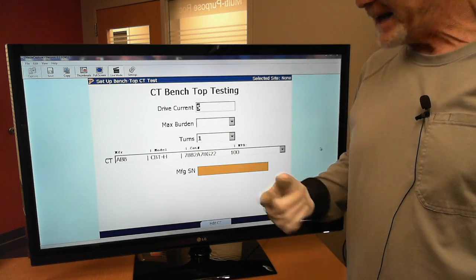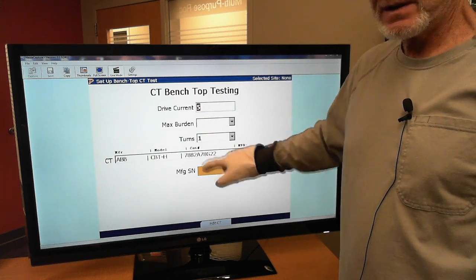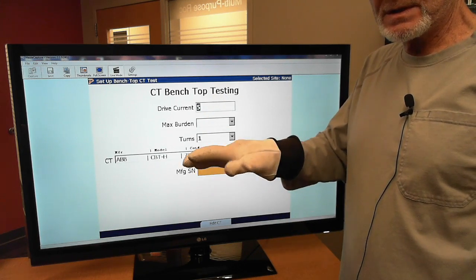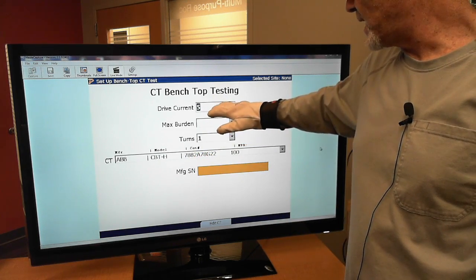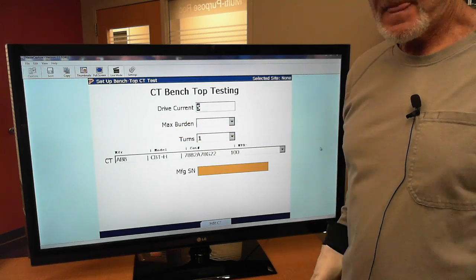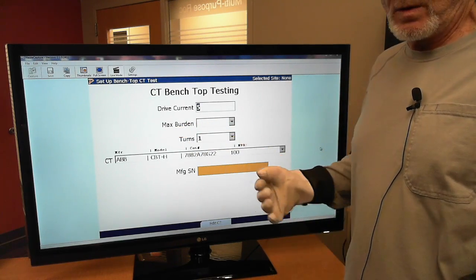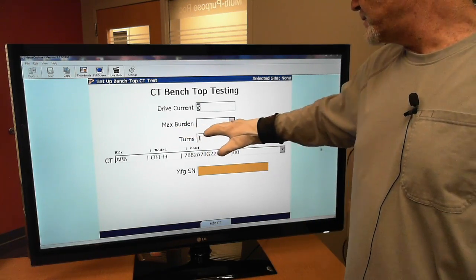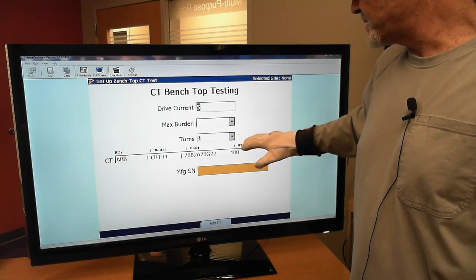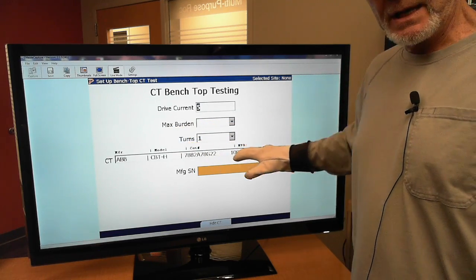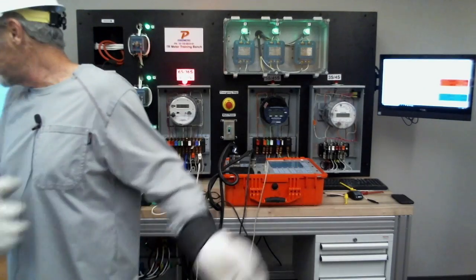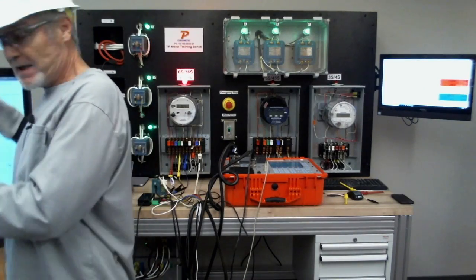It's a 200 to 5, so I'm going to drive 20 amps through there, putting me at that 10% mark, which ANSI tells us is the good mark—we say that a lot. I'm going to max burden; I can go all the way up to 4, but I'll just go half an ohm, which we've been doing pretty consistently throughout our webinars. I'm just going to do the 1 turn again. You'll notice it's similar to the screen we saw earlier with the boost test, except this time it's not in service.